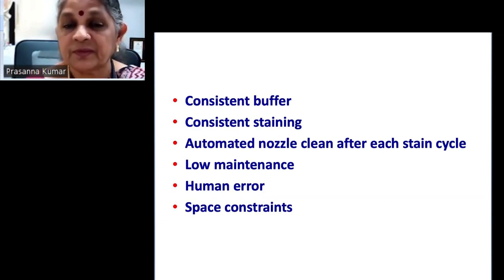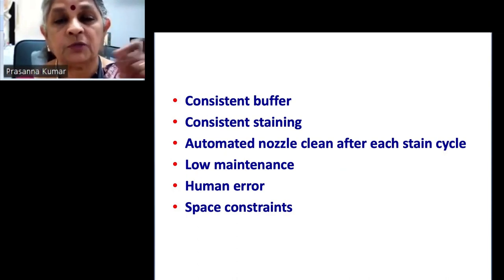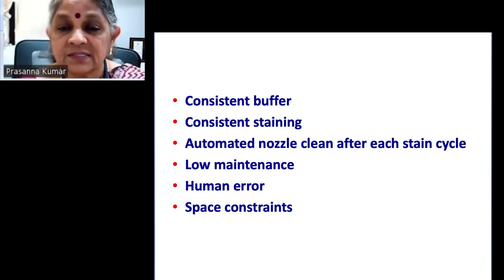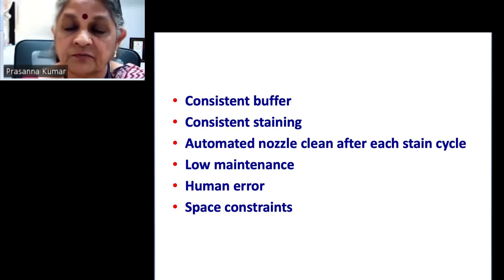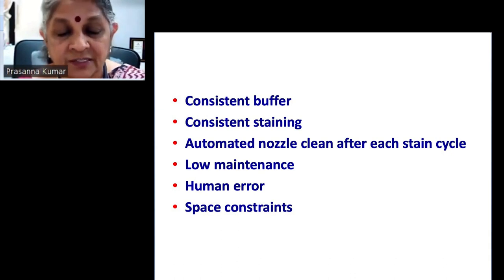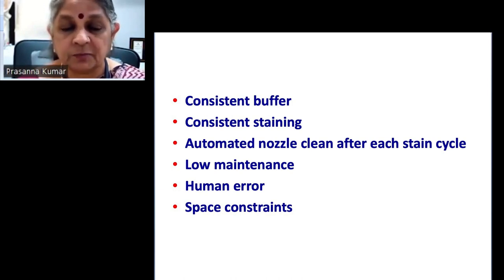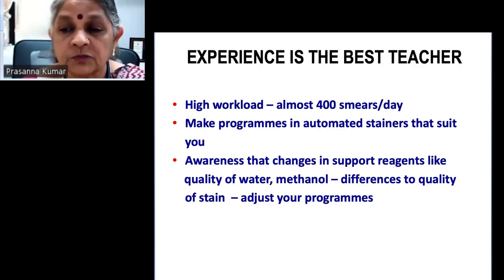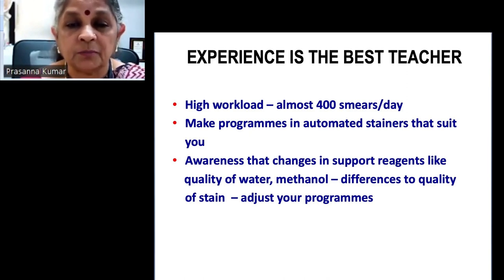There's consistent buffer and consistent staining via an automated nozzle — no more checking buffer pH with paper each morning or adjusting with acid or alkali. The nozzle is cleaned after each stain cycle, and this instrument has very low maintenance. Chances of human errors — forgetting to pH the buffer, not standardizing — are eliminated. The machine occupies only about one and a half by one and a half feet, so space constraints are also addressed.